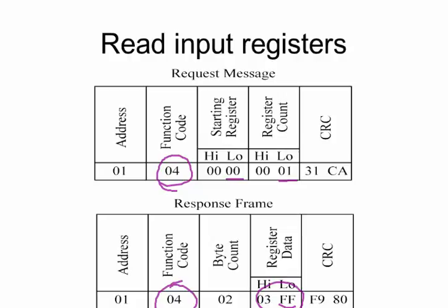It's an input register. So if this was a 16-bit input card with discretes coming into it, then it's telling you that the low 10 are on. Again, it's all about understanding what that register represents inside the PLC or the device that you're communicating with, because it may not be a PLC. I'm using ModBus to talk to energy meters, so that could well be an indication of the voltage, or the accumulated kilowatt hours.